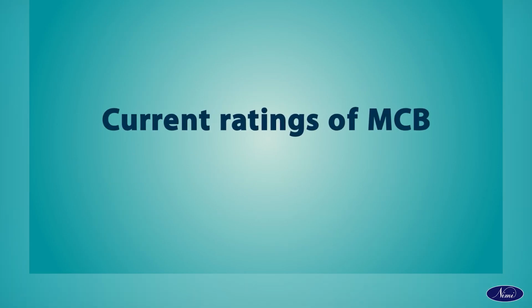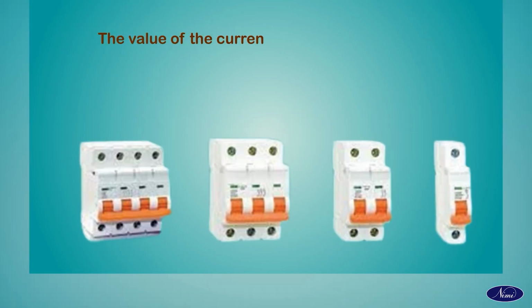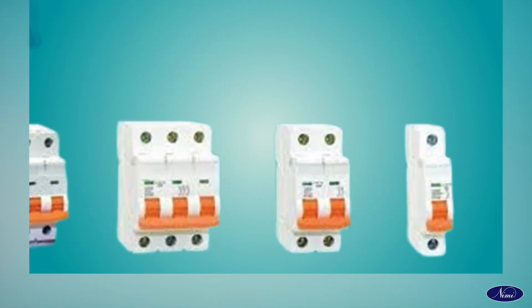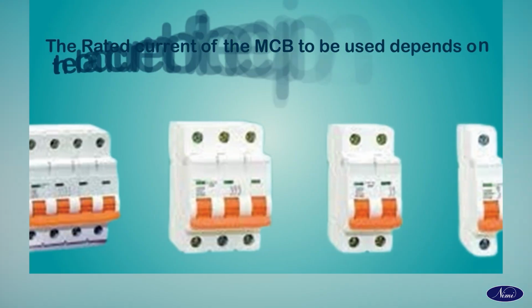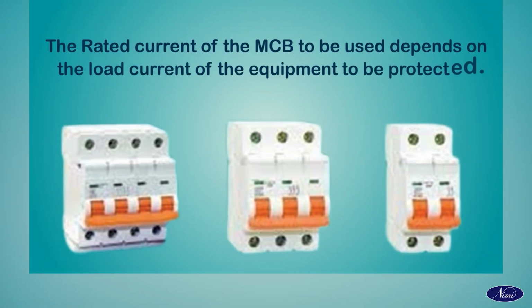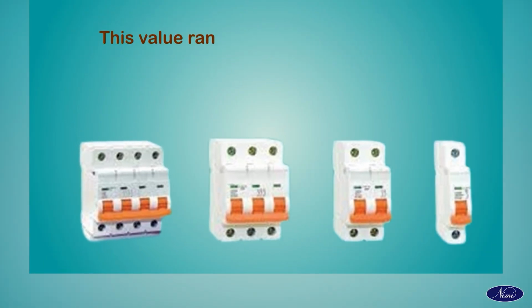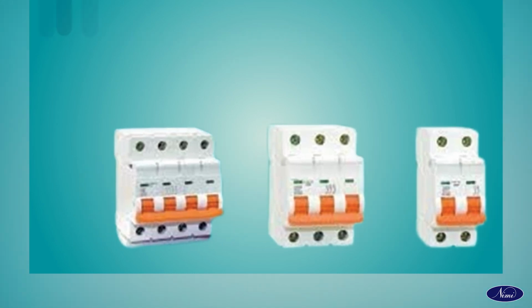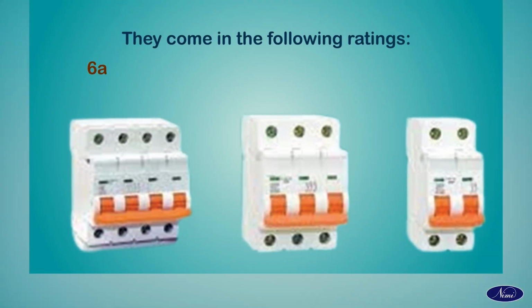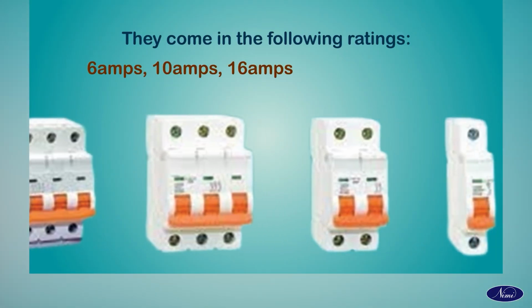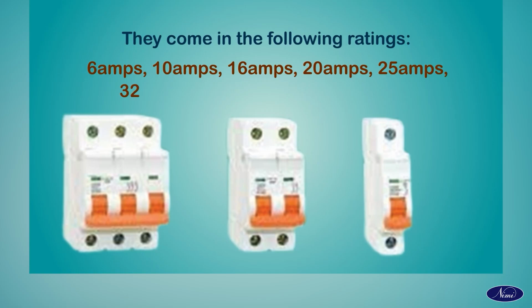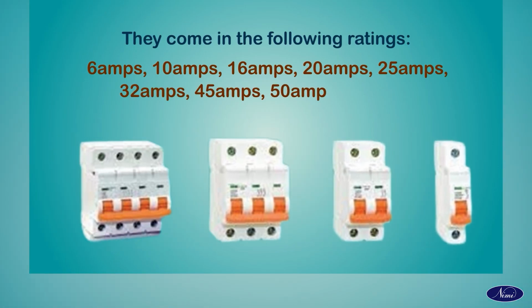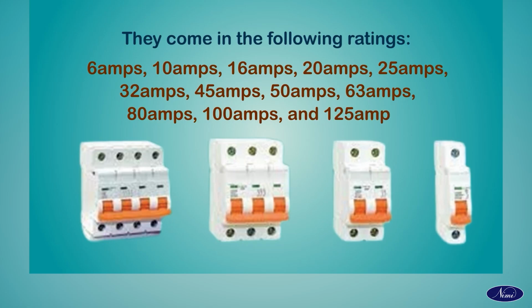Current ratings of MCB. The value of the current over which the breaker trips is known as the current rating. The rated current of the MCB to be used depends on the load current of the equipment to be protected. This value ranges from 6 to 125 amperes for a standard MCB. They come in the following ratings: 6 amperes, 10 amperes, 16 amperes, 20 amperes, 25 amperes, 32 amperes, 45 amperes, 50 amperes, 63 amperes, 80 amperes, 100 amperes and 125 amperes.